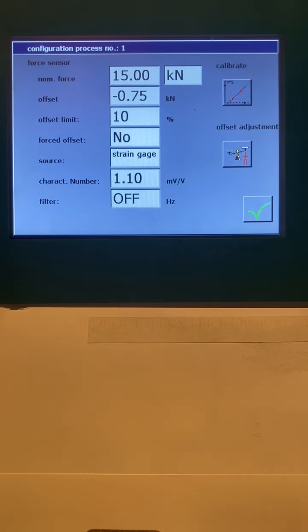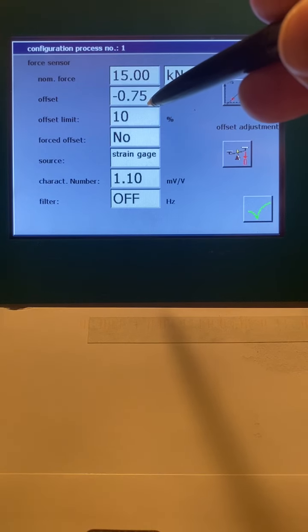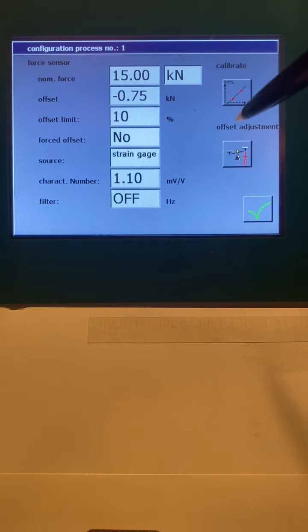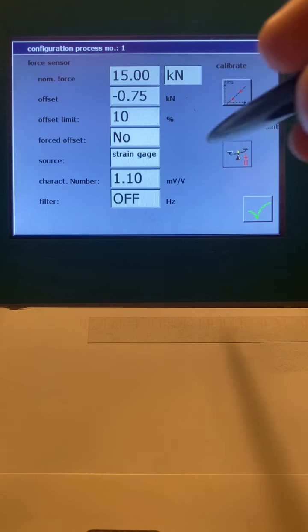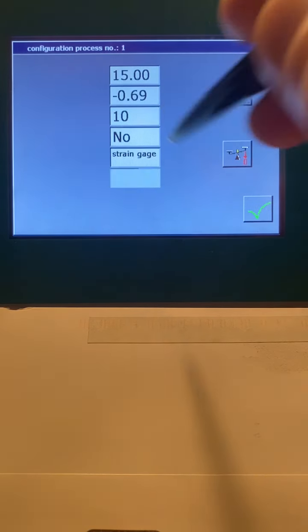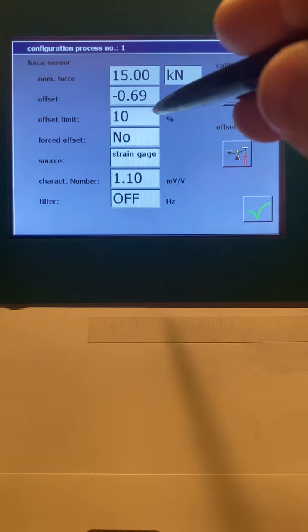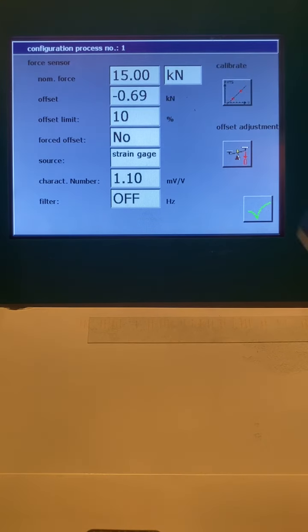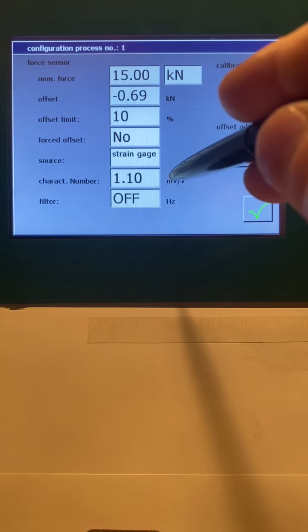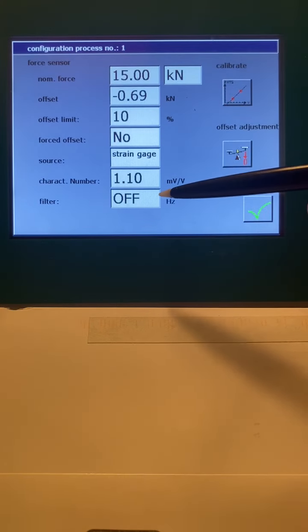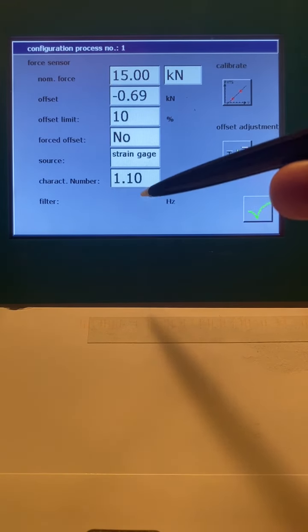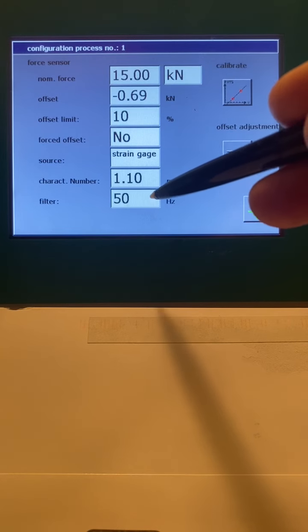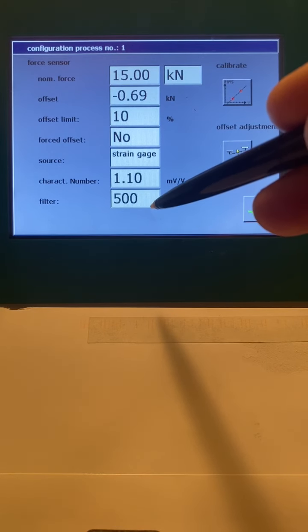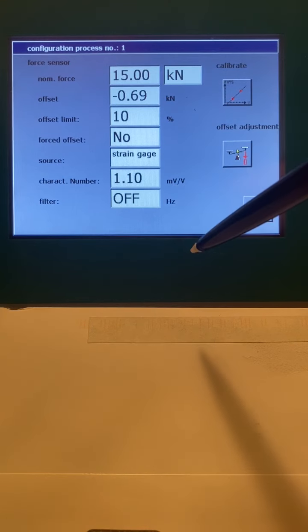My offset is, where is zero? So you may have some tooling that's hanging on this, and you may want that tooling not to be registered, so you'd put an offset on here. Your offset limit is a percentage, so that if I zero, and my offset limit is greater than 10%, it's going to give me a problem. It's going to give me an issue. Strain gauge, here's my millivolts per volt if you're using a load cell, and my filter. I can do a filter of 5, 10 hertz, 20 hertz, 50, 100, 200, 500, 1,000, or off.